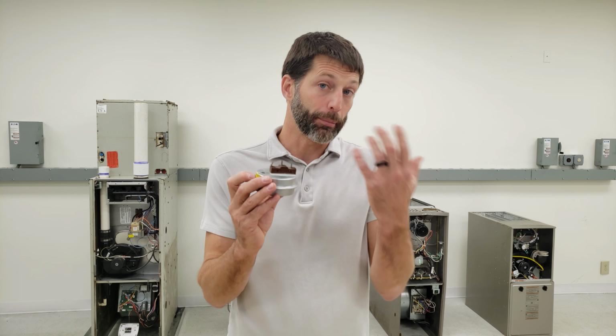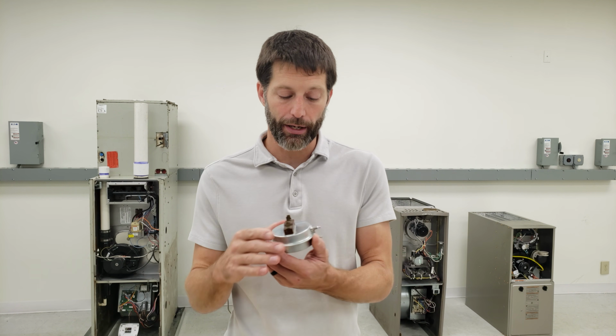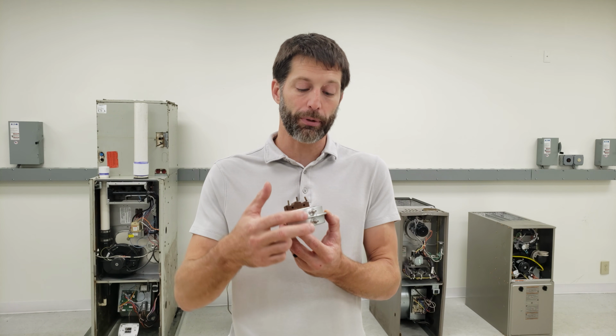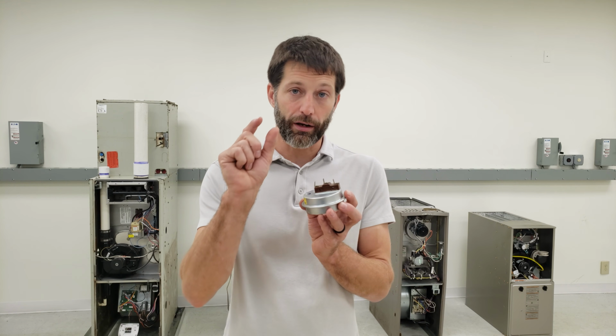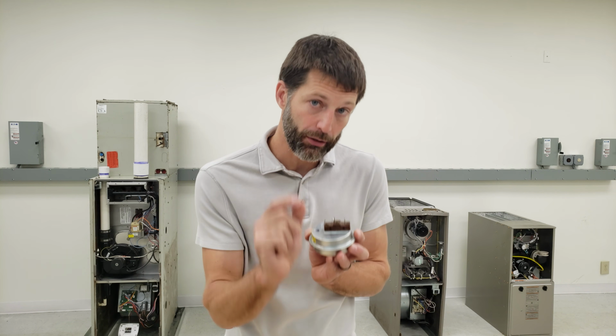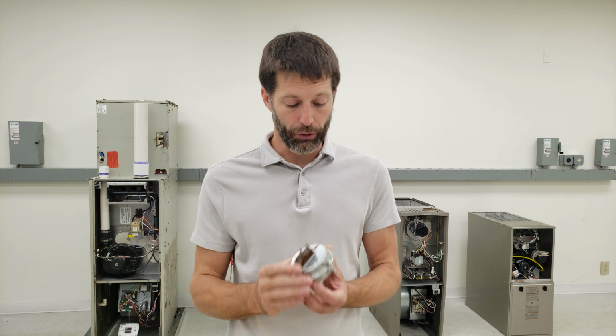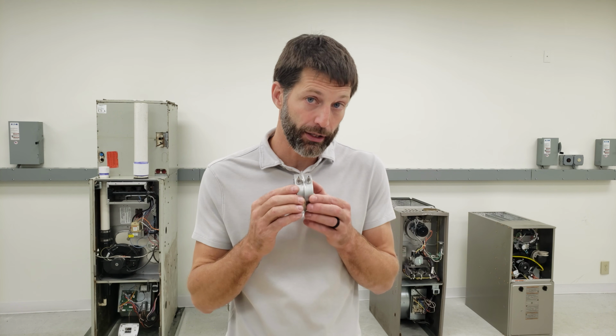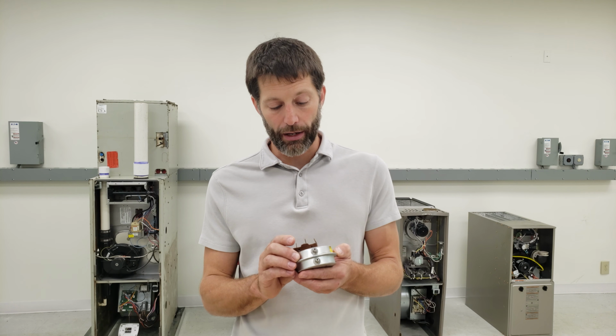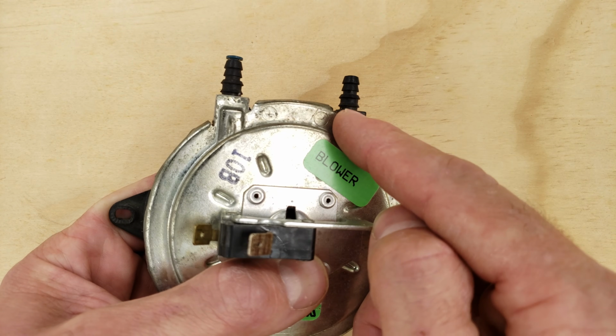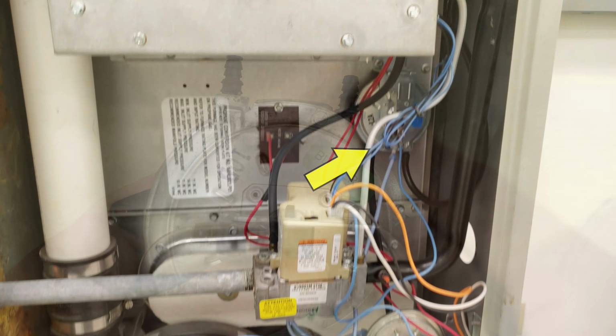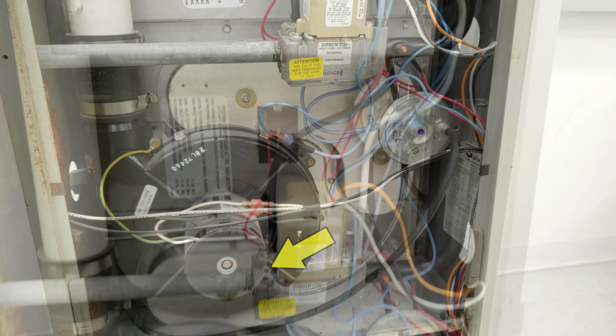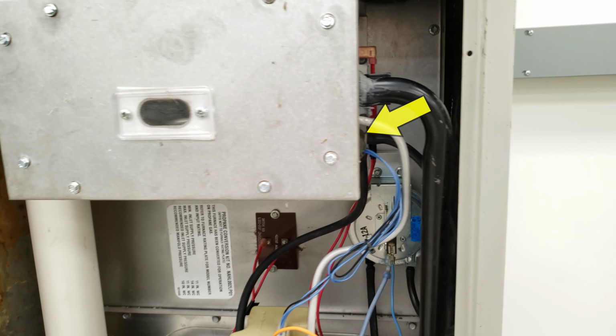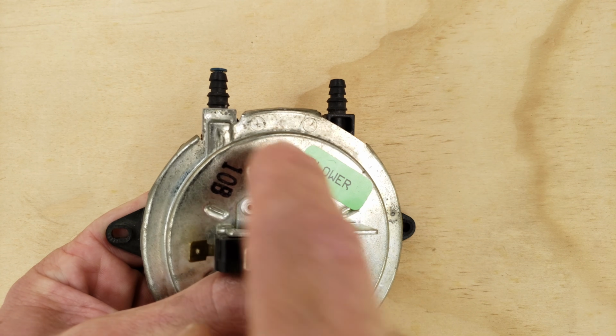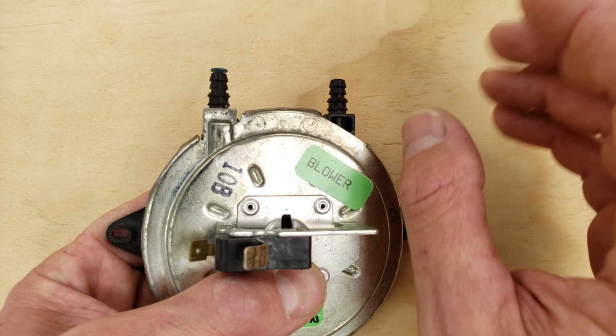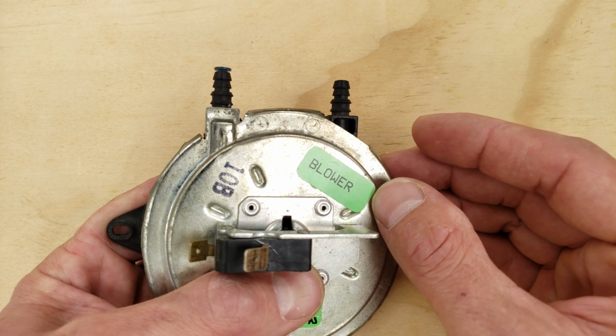And then you also have the possibility of having a three-terminal pressure switch. The three-terminal pressure switches typically have two ports on them. So you have one set of normally open contacts and the other set of normally closed contacts. You're looking at a pressure differential across the pressure switch, and typically you have a positive and a negative. On this two-port pressure switch, you see a positive and a negative. The negative one typically goes to the inducer motor, and then the positive typically goes to a combustion chamber. This is used typically on a sealed combustion furnace, and they're usually a 90% efficient furnace or higher.